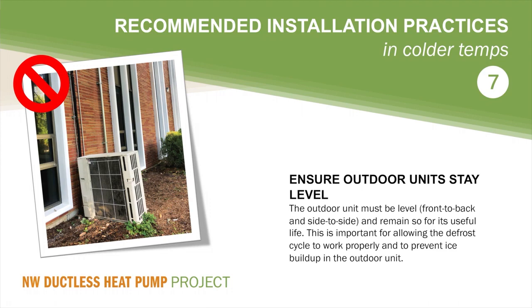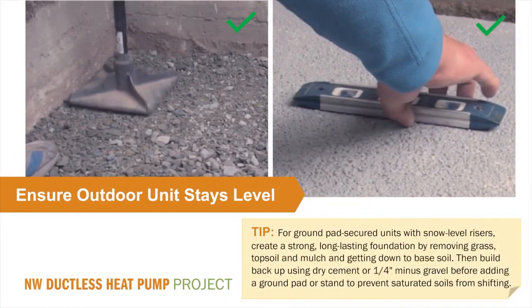When installing outdoor units on the ground using a pad, you must have a strong, lasting foundation for the pad itself, and this involves removing grass, topsoil, or mulch and getting down to base soil. Then, add dry cement or 1/4 inch minus gravel to build back up. Pack this material and level against the ground pad. Then install the outdoor unit on top of that using riser blocks. When installed this way, an outdoor unit can stay level for its useful life and remain above the snowfall level requirements of the local building code.